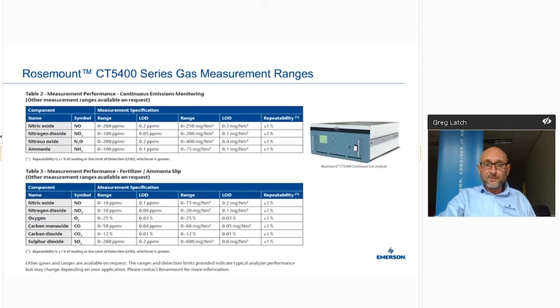That's good fun. So just as a little summary as we're heading down to the last of it here, with regards to hot, wet, speed of response for CEMS - absolutely, response is key if you do want to start to implement control strategies. Some of the applications I've had over the years can be very scary with regards to trying to implement control strategies, utilising feed forward, depending on load of plant. Feedback is the space we're looking at in this particular case. There could be feed forward, for example, within the space of gas composition being fed into your combustion process, or even in a liquid space with specific gravity.